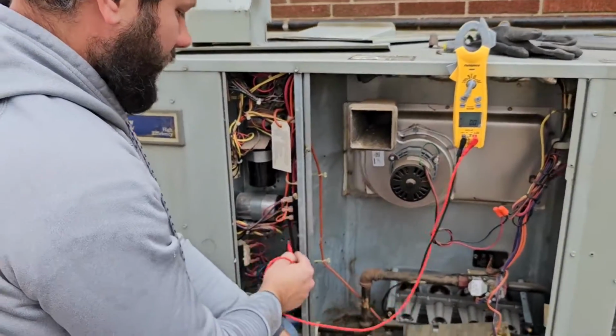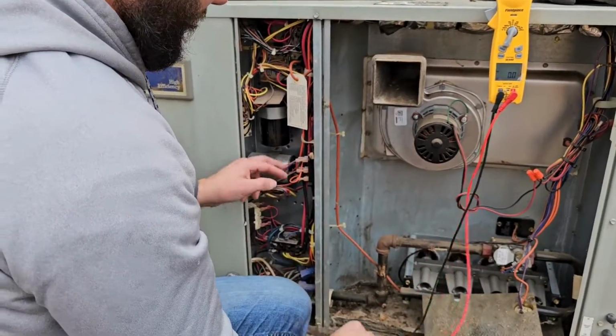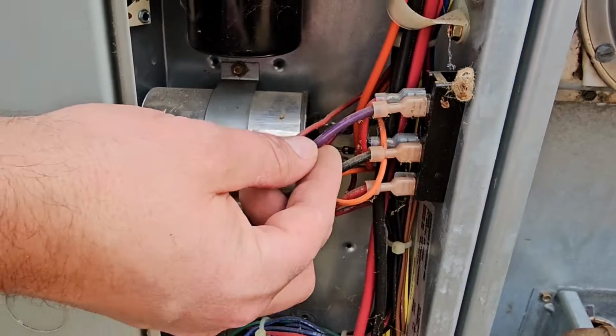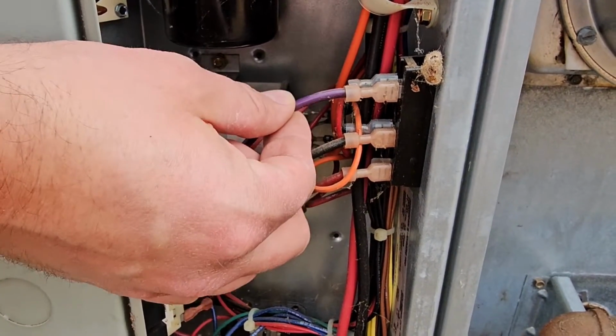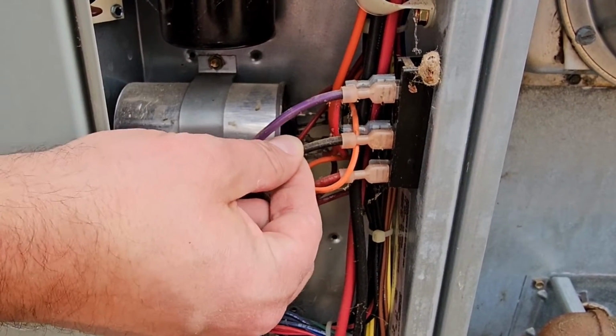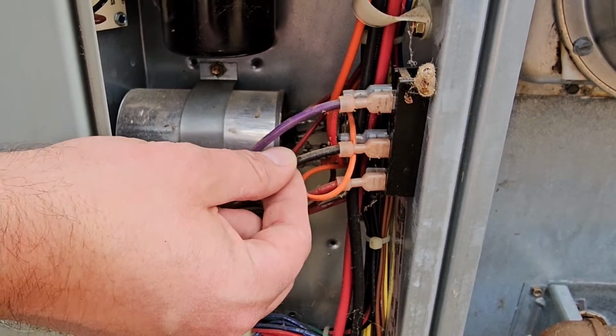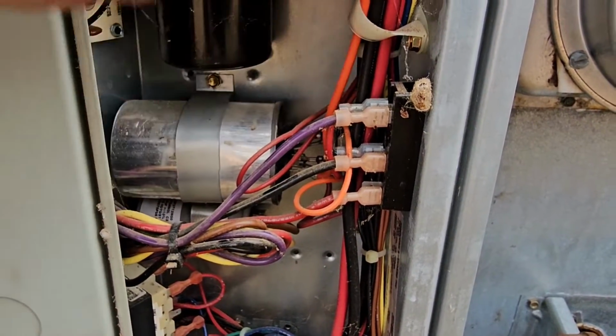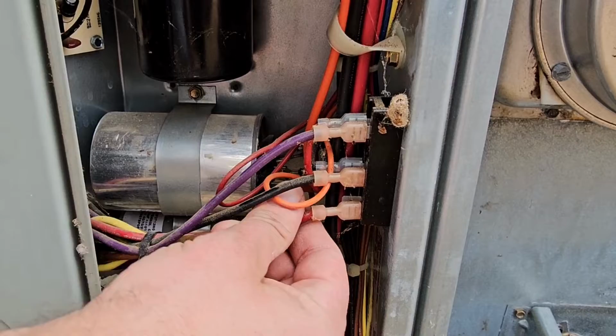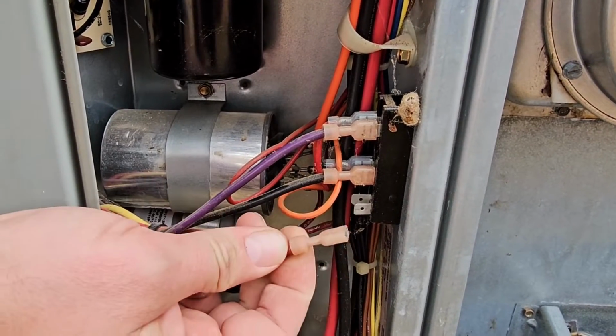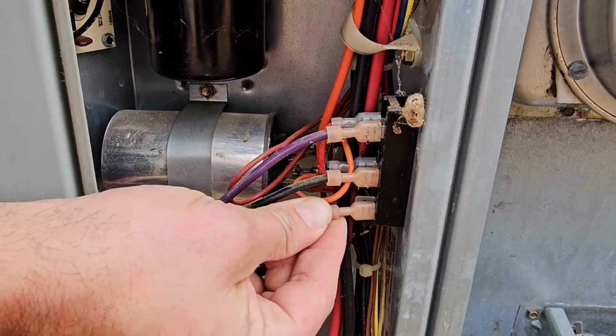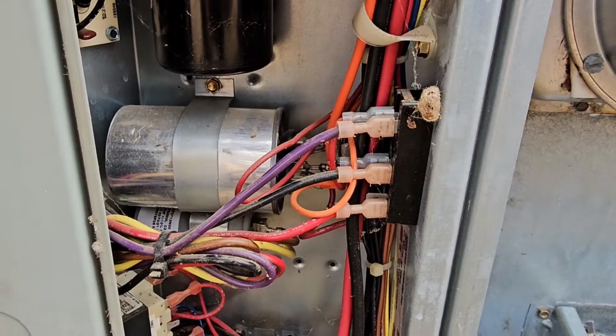Here are our indoor motor wires. See this? We got a purple and a black. You see this? This is the common wire for the motor. This is the speed wire. All right? And these wires that connect to it run back to the board. This is basically an empty terminal. This is the low speed. The black wire is the high speed.